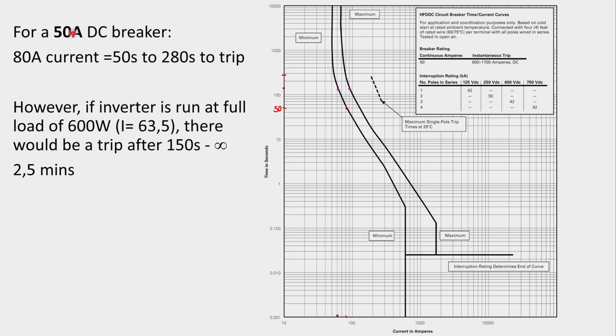That means that if I use a 50 amp circuit breaker, it might trip after 2.5 minutes, but it might never trip. So that means that under full load conditions, there's a chance that the circuit breaker will trip, and there's a chance that it will never trip. But what is rest assured is that at 80 amps, it will trip, although not very fast. It'll trip after 50 seconds to a maximum of maybe 260, 270 seconds.